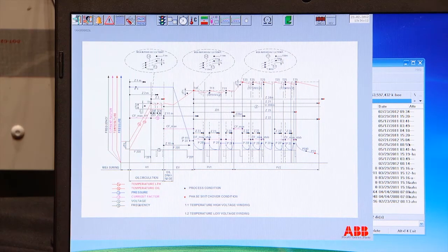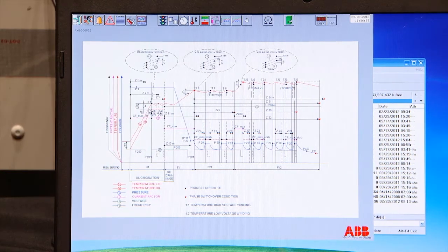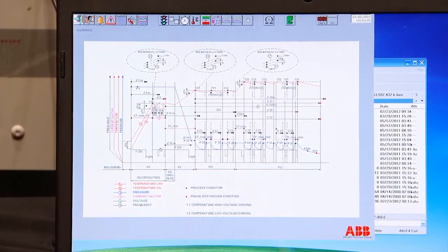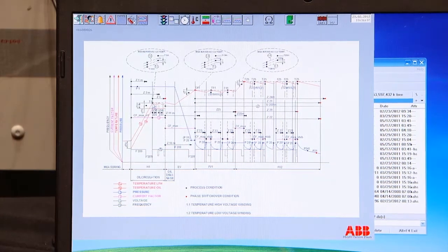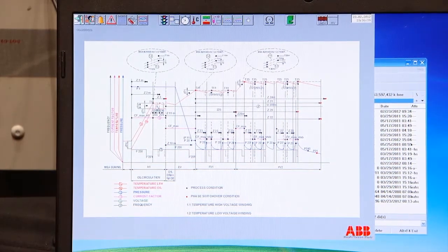So looking at this picture here, which is describing the process, we have been heating up from our initial temperature value to our set point. In between here, you have your 5 degrees when you're taking your high voltage readings, and then we're heating up here. So now we are at point T1, stopping, and the temperature will drop. After half an hour, we'll take a new reading and heat up again.